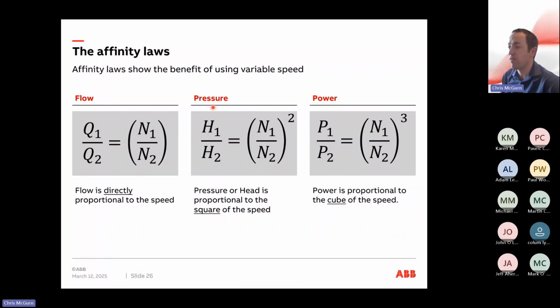So why do VSDs improve the efficiency at lower speeds? There is a calculation law around this, and it's something called the affinity laws, which shows the benefit of running flow at lower speeds. So these are the calculations here. Flow is directly proportional to the speed. The pressure is proportional to the square of the speed. And the power you use is proportional to the cube of the speed. Okay, so these are all part of the affinity laws.